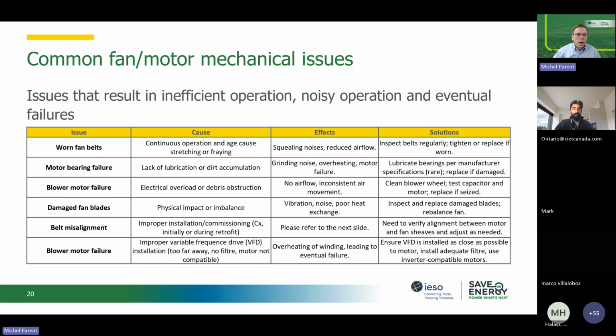When you change the belt, you need to make sure that there's proper alignment between the sheave of the motor and the fan. And there again, the table, I'm not going to read everything in that table, but this table provides you the effects, so what you can use to diagnose a problem with misalignment of your motor sheave and your fan sheave. And you want that to be properly aligned. Sometimes you get tensile failure of your belt. That's usually a very good sign that you have misalignment. If you see that your belts are wearing too fast, if you see black dust at the bottom of the belt, that's usually a sign of misalignment.